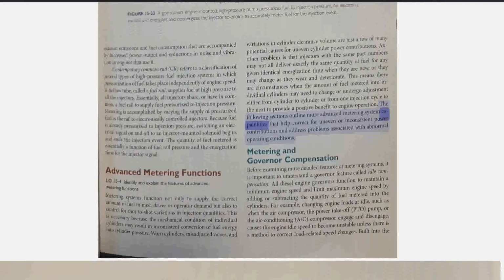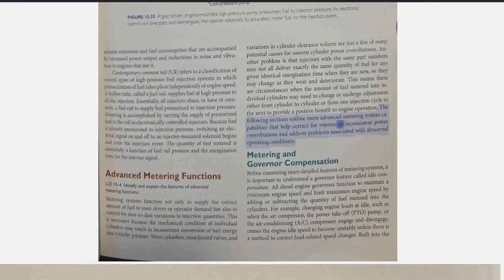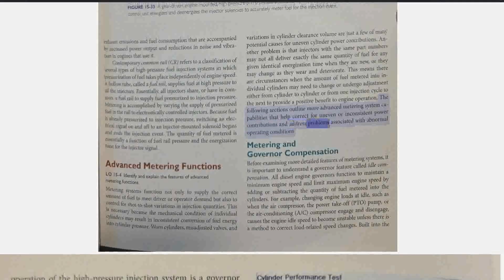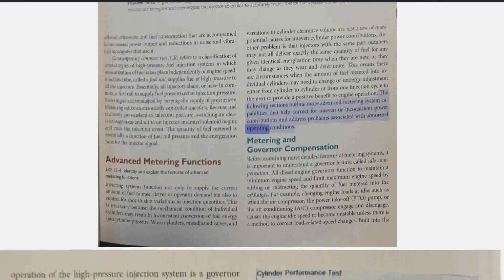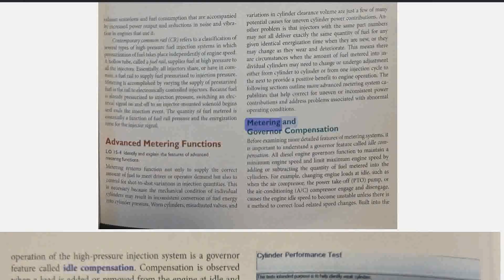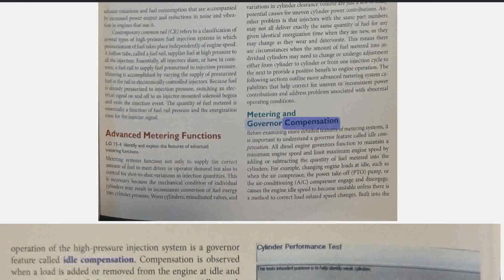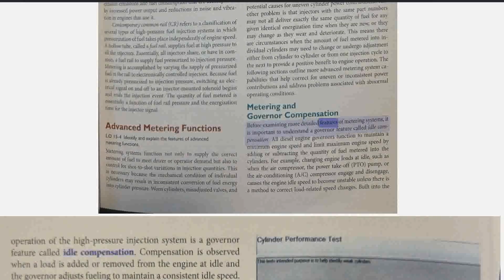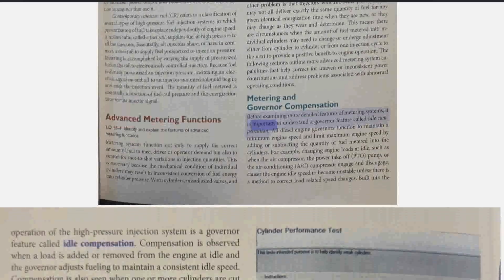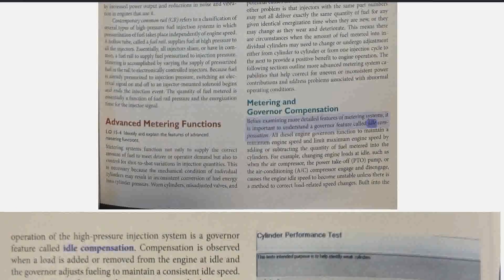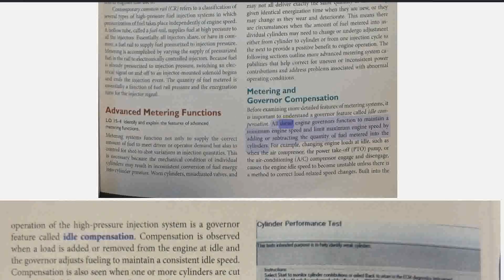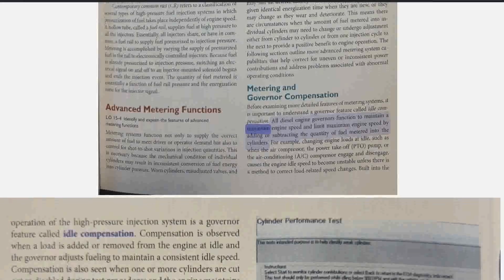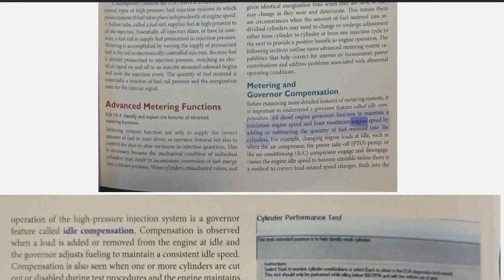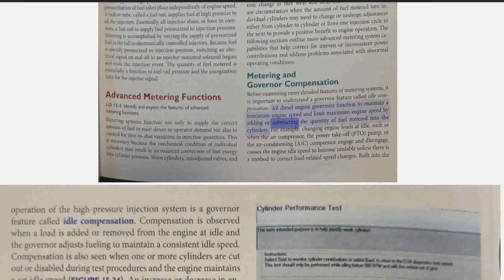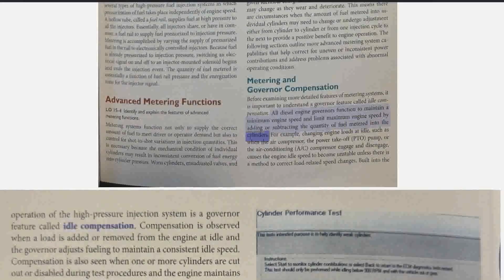The following sections outline more advanced metering system capabilities that help correct for uneven or inconsistent power contributions and address problems associated with abnormal operating conditions. Metering and governor compensation. Before examining more detailed features of metering systems, it is important to understand a governor feature called idle compensation. All diesel engine governors function to maintain a minimum engine speed and limit maximum engine speed by adding or subtracting the quantity of fuel metered into the cylinders.